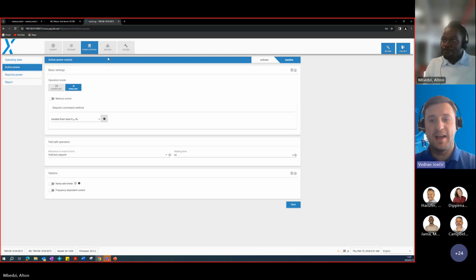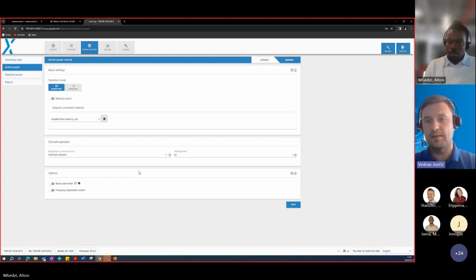I hope this is clear to everybody, because zero feed-in is a huge topic in South Africa. What was just done, opening this small setting button and entering a 0 at this point, that's everything you have to do to assure zero feed-in operation with the BlueLog. There's nothing else — of course you have to set up initially the BlueLog and prepare everything, and connecting these devices will be shown separately. But from the power control point of view, this is the only thing you have to do, and this is really an advantage of using a BlueLog. Comparing it to other solutions in the market, you do not have anything to program or go into detail, because everything is pre-programmed here, and you just enter the values you're interested in for how to operate your system. This was a click and done within 50 seconds. So if everything is set up right on site, it doesn't take that long to commission the site.